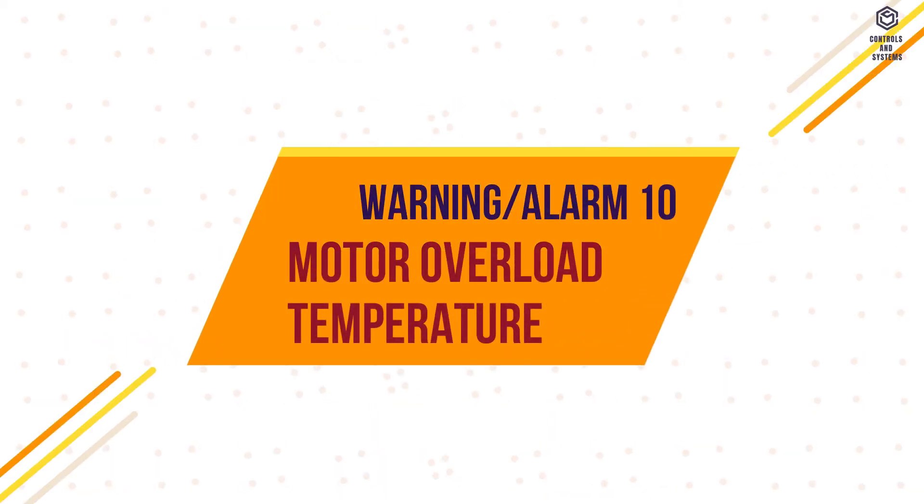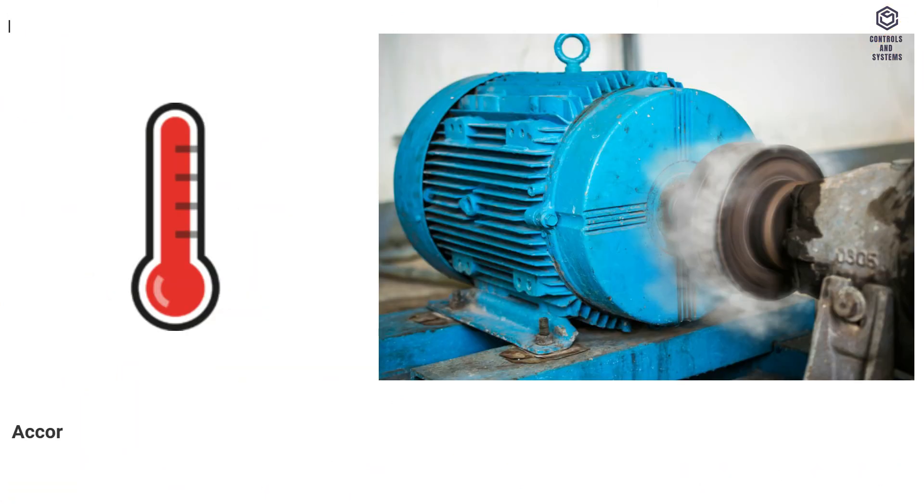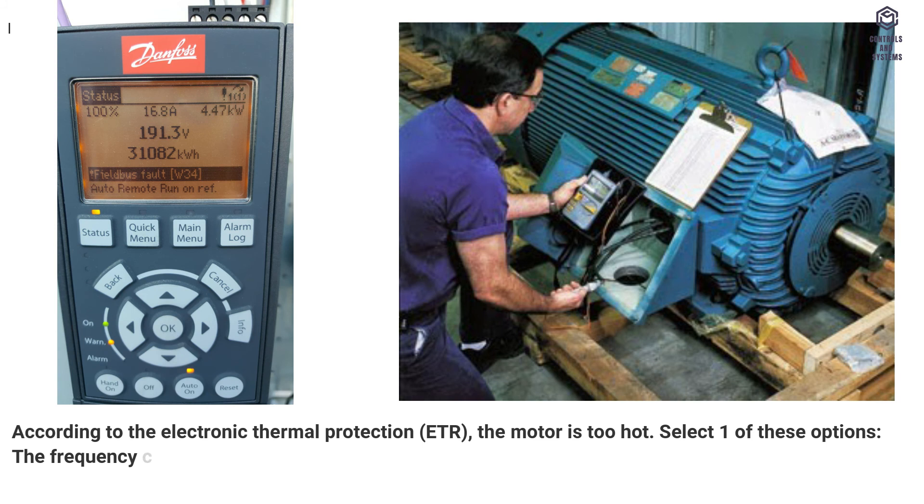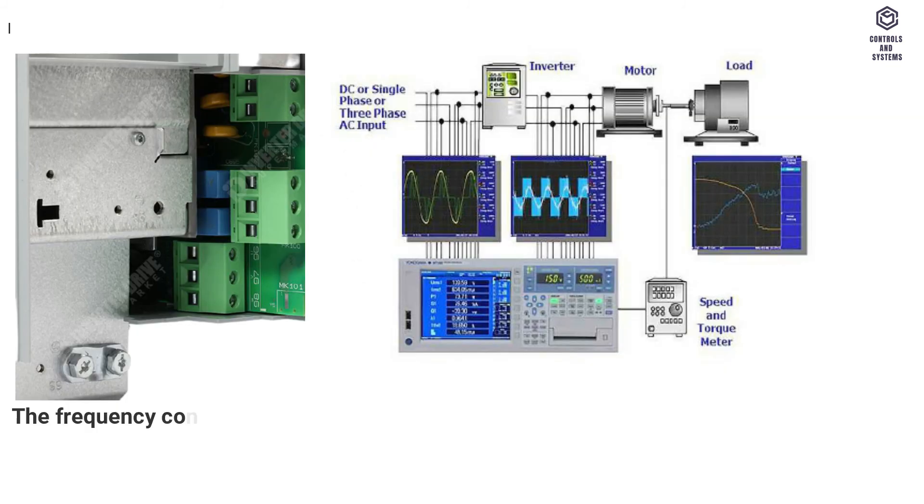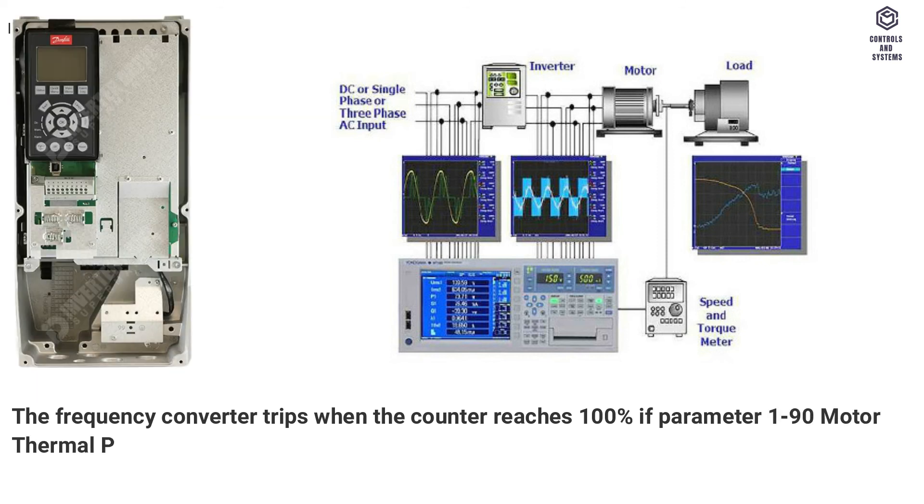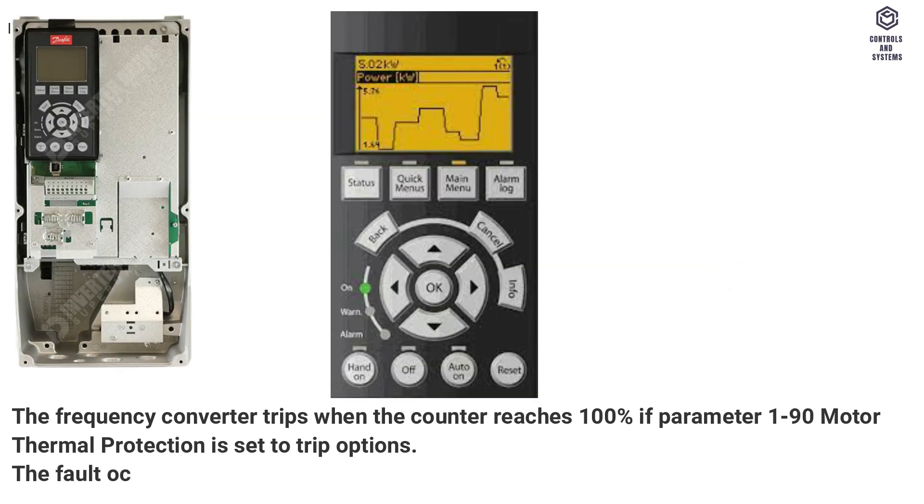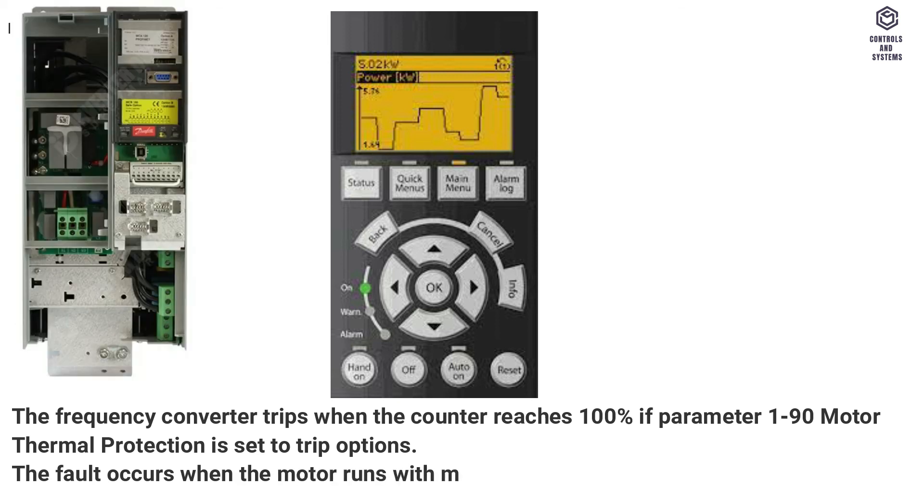Warning, Alarm 10, Motor Overload Temperature. According to the electronic thermal protection, ETR, the motor is too hot. Select one of these options: The frequency converter issues a warning or an alarm when the counter is greater than 90% if parameter 1-90 motor thermal protection is set to warning options. The frequency converter trips when the counter reaches 100% if parameter 1-90 motor thermal protection is set to trip options. The fault occurs when the motor runs with more than 100% overload for too long.